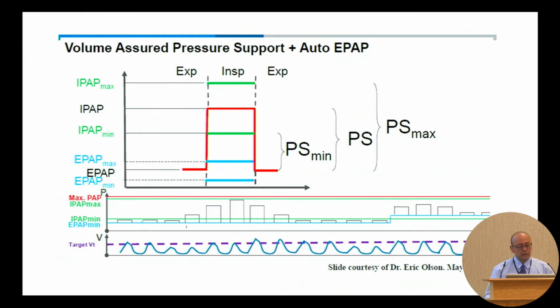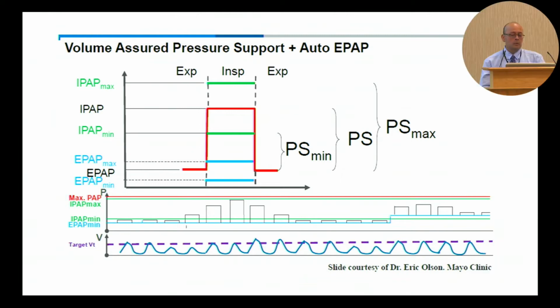This is a good slide because it tries to combine what we used to do before 2010 and what AVAPS is. So you see the red line, the red graph, that's plain BiPAP S. You have your EPAP, it goes to IPAP, maintains the IPAP pressure for the time determined, and then goes back to EPAP. What you see in the blue line is the AVAPS algorithm, which has auto EPAP basically. The EPAP is automatic. And then you have the other two settings that you give your machine: a minimum IPAP and a maximum IPAP.